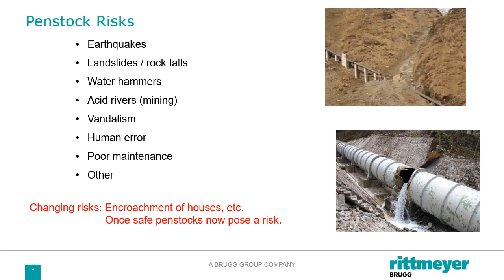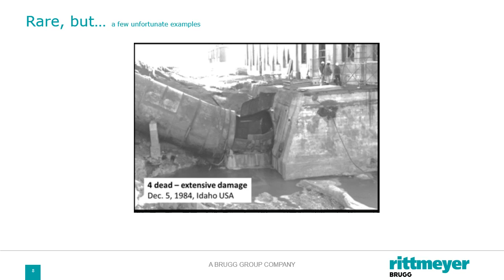Fortunately, penstock ruptures and disasters are rare, but they do happen. Here are a couple of examples. In 1984 in the USA, this plant experienced a water hammer and sustained quite a bit of damage. There were 5 people working inside the powerhouse at the time. They were swept out through a hole torn through the other side by the surge, carried downstream, and unfortunately 4 of them did not survive.